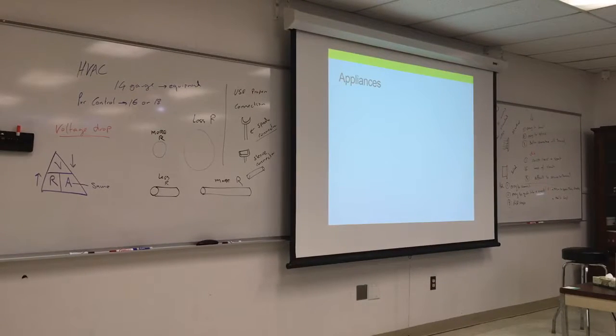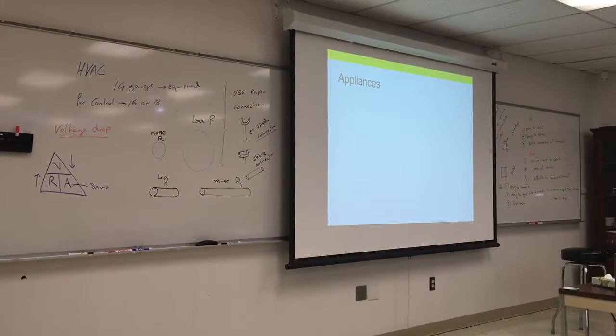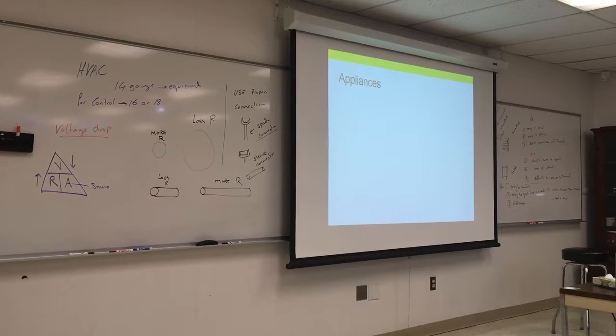This room is very warm because we have 32-33 people in it. Should we design for when it's full or empty? When it's empty — that's why it applies to heating. For cooling, you design when the equipment is on, people are there, because the AC needs to keep up. For heating, if people and equipment are there that's good, but you can't count on that.